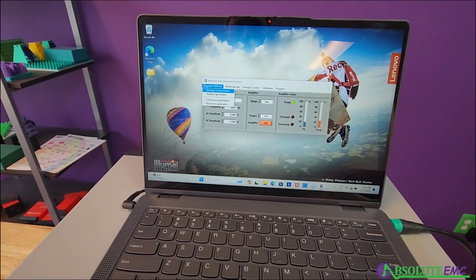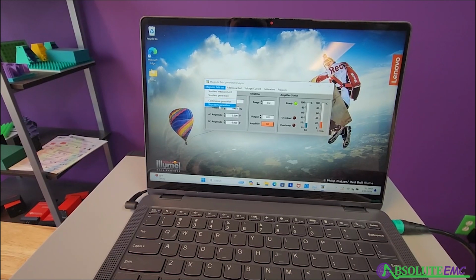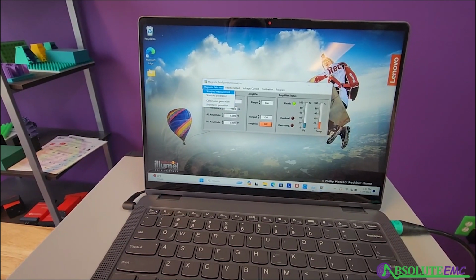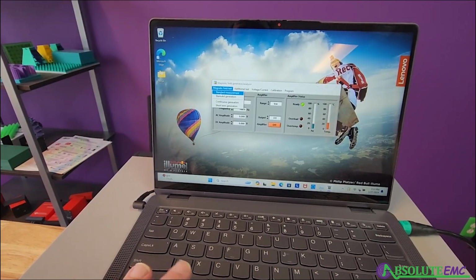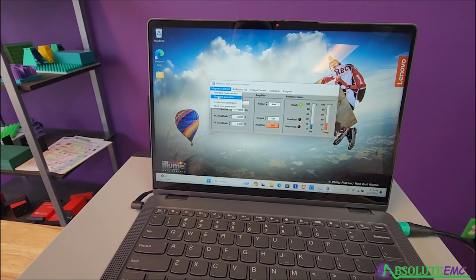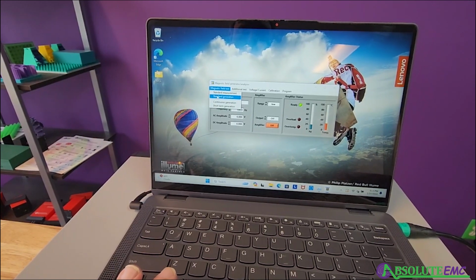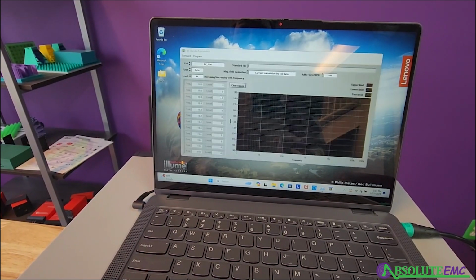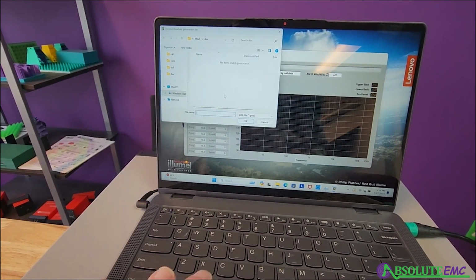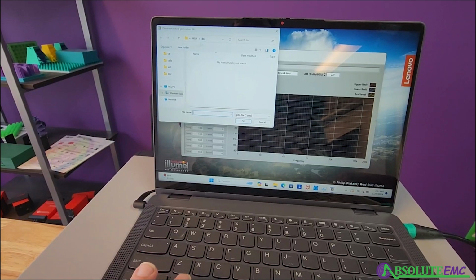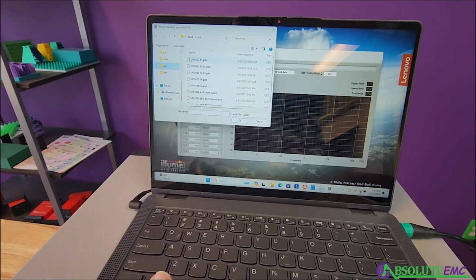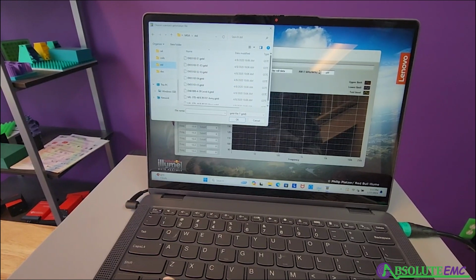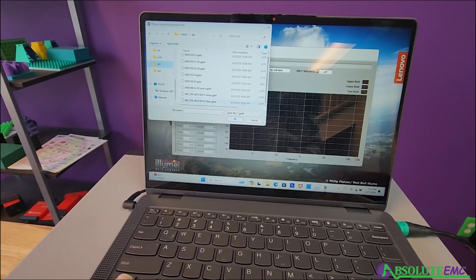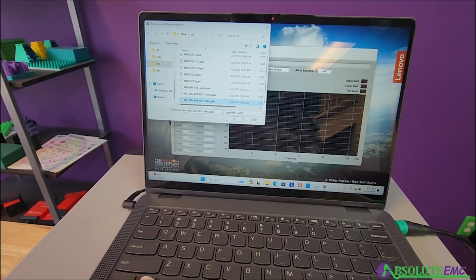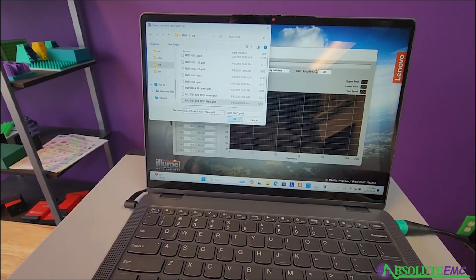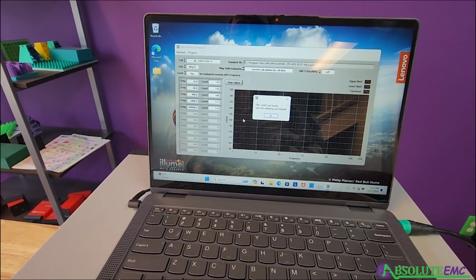And we have standard measurement, standard generation, continuous generation, and short-term generation. Standard measurement, which means you're going to measure emissions. Standard generation means that you're going to generate a field. So first we're going to do that. Do a test, and then here it's going to come up and ask for a standard to run. All right, we go to standard, and we'll start with, say, Navy. Okay, you just need to select one actually to start off with, and we can change this and save it as a different name as needed.